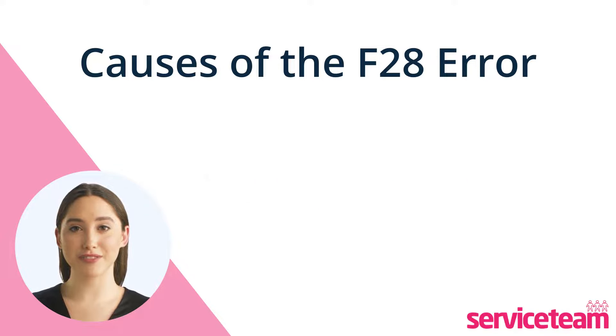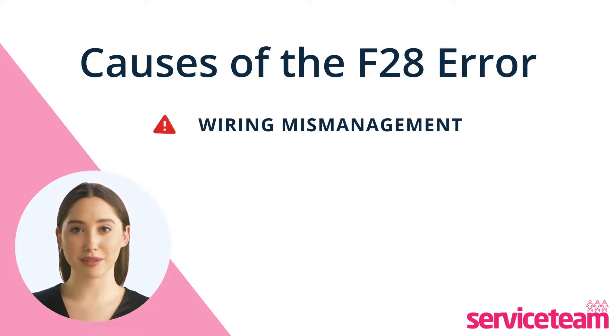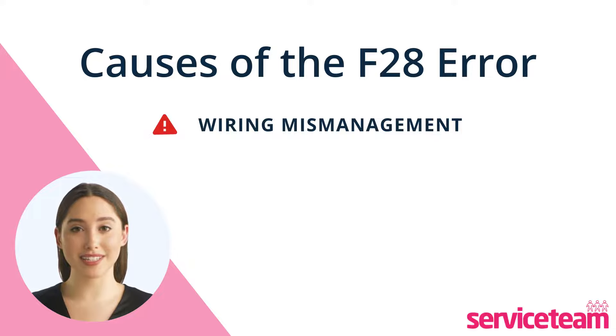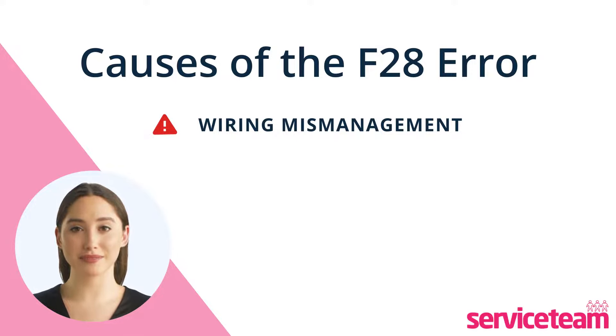If wires in a heating system are improperly connected or damaged, wiring mismanagement can disrupt communication between essential components like the gas valve and PCB, resulting in an F28 error.